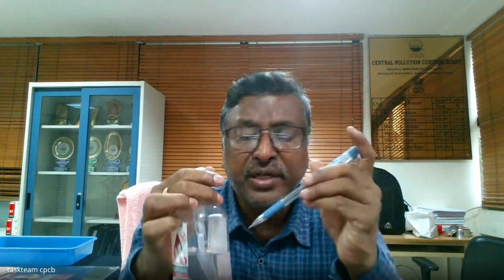Why a plastic bottle is preferred: because if there is a fall, it is not going to break. Half filled means in order to control vaporization. Therefore, it will be there as part of the water only. Now, this is the procedure to collect the mercury balls which you can see with your naked eye. Now, the second one is mercury balls on the floor which you cannot see with your naked eye.